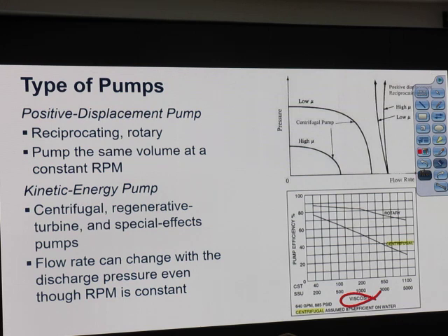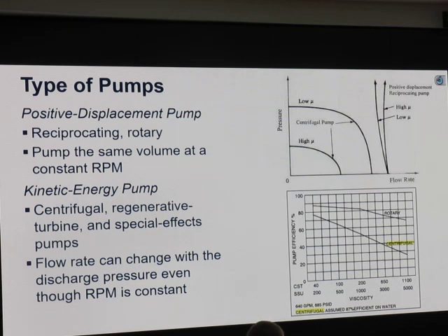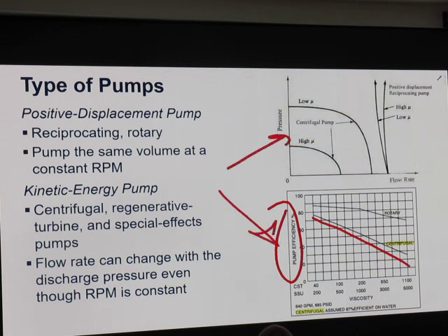Sometimes they tell you the viscosity in units like Saybolt seconds. What kind of viscosity is that? There is dynamic viscosity, and kinematic viscosity, which is mu over rho, right? Saybolt is a kind of mu over rho. It's not mu, so be careful with that. Look at the pump efficiency. The pump efficiency goes down when the viscosity of the fluid goes up, right? We need this kind of chart to size the pump.